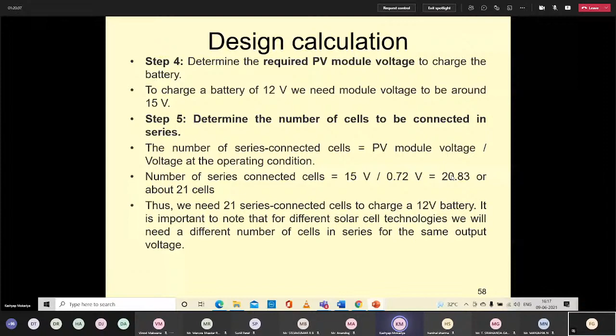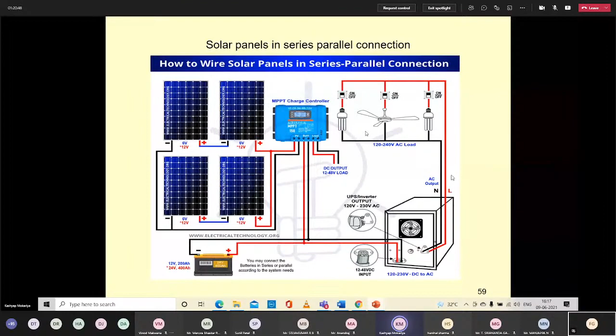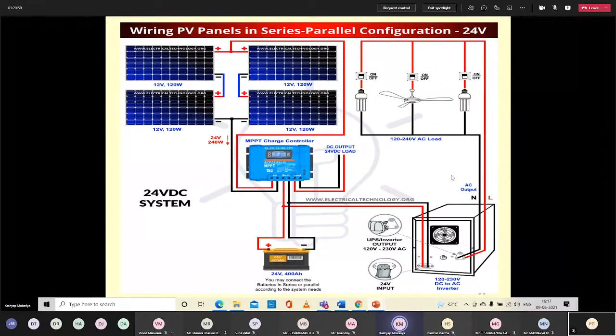This I have explained in one of the slides: how the 24 volt two batteries were connected in a series-parallel combination to meet the desired capacity of a charging station. While this type of application is there, we know that my charge controller is there, my panels are there. This might be any load, a combination of an EV charging station or a combination of a load and a domestic load, or only EV charging station load. That depends upon what application or what design you have in hand at present. So this is one more design for a 24 volt system that you can go for.